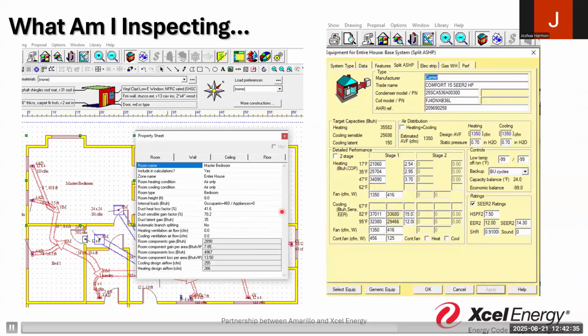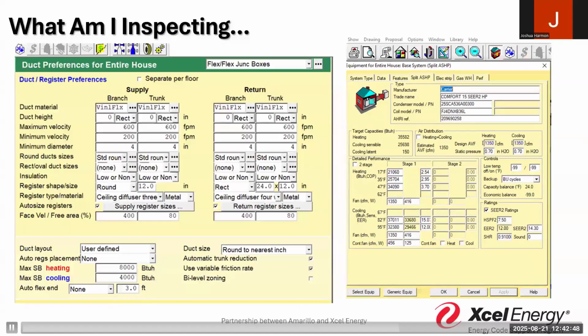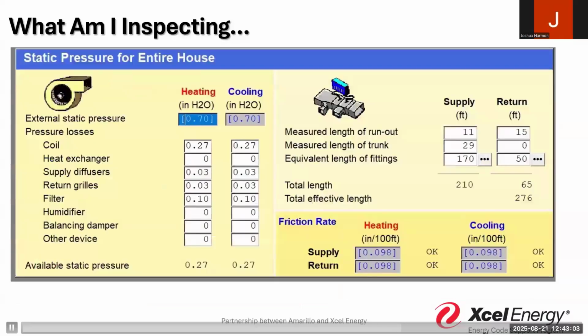It requires the designer to take the time to recognize the capacity of the equipment, the different heating loads, the ventilation requirements, the types of static pressure, and the size and design of those duct systems. Are they going to be round ducts or square ducts? These are things that need to go into the original design, and that consideration needs to come out in the actual project.